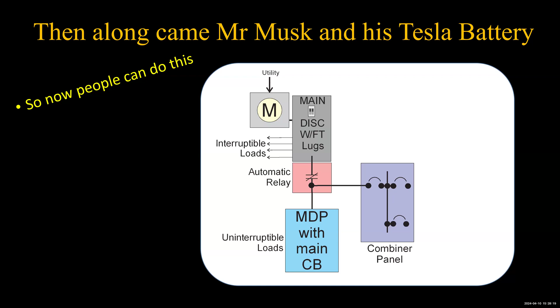And now we can't see the reason yet until we bring in a combiner panel, which still doesn't have anything to feed the uninterruptible loads. But if we add a little bit of solar, then we do have uninterruptible loads if this PV inverter can keep operating when the utility goes down. That's interesting—there are some out there that'll do that.